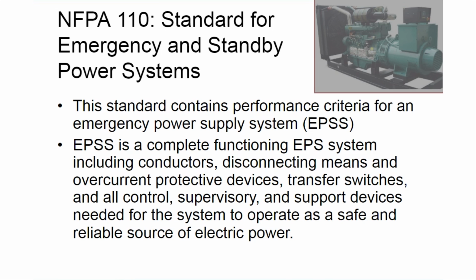This can be a little confusing when you try to relate it back to NFPA 70, which we'll get to in a minute. Things aren't always defined exactly the same way within these code sections, and you have to be very careful how you read them and understand how to interpolate between the codes. Some of the other relevant criteria in NFPA 110 include the testing of an EPSS. It requires an EPSS to be visually inspected every week, and it requires it to be run for 30 minutes monthly at 30% load, and it requires all transfer switches to be tested monthly.